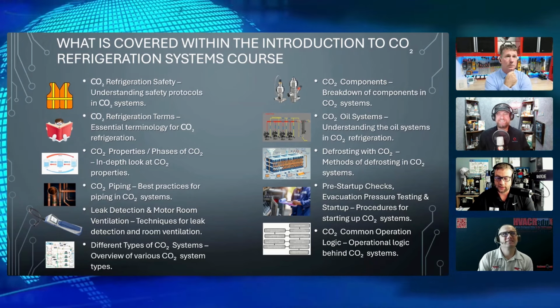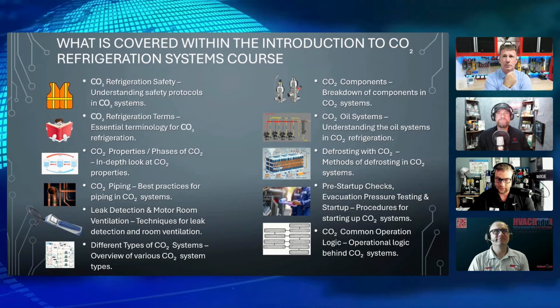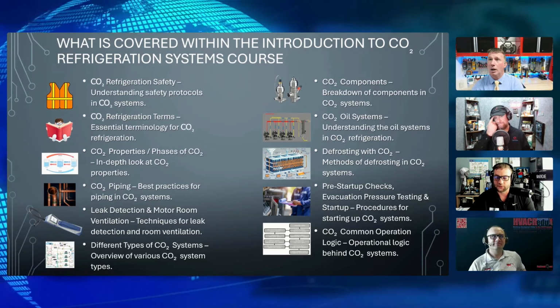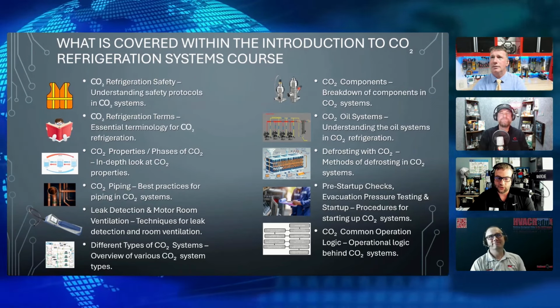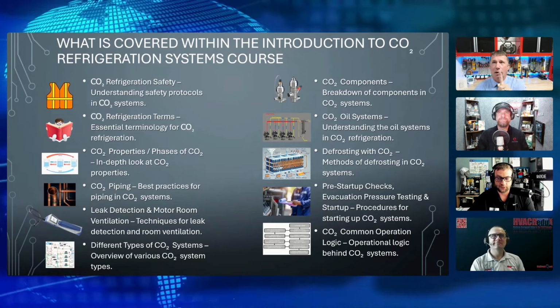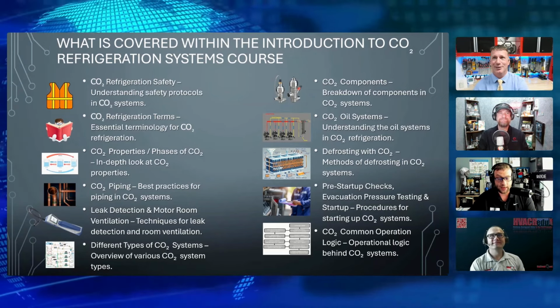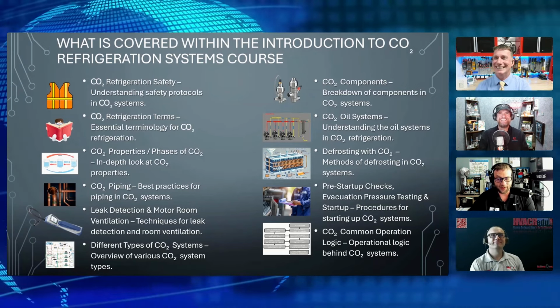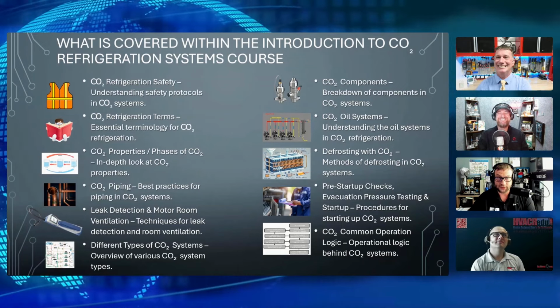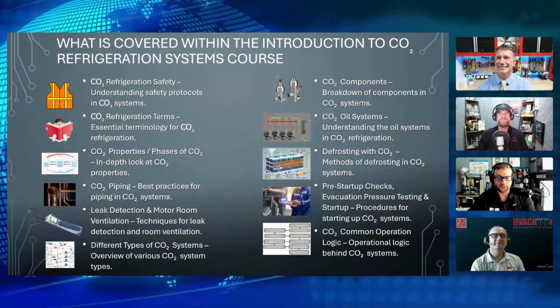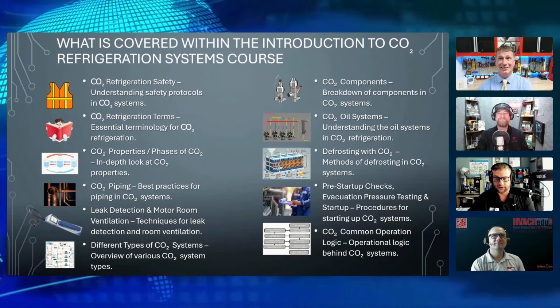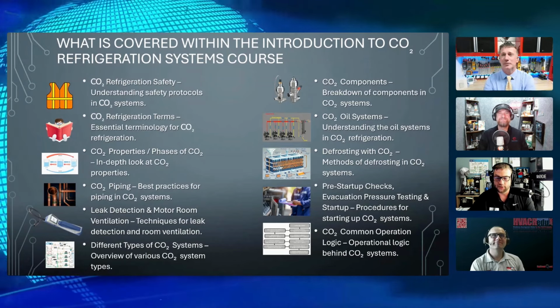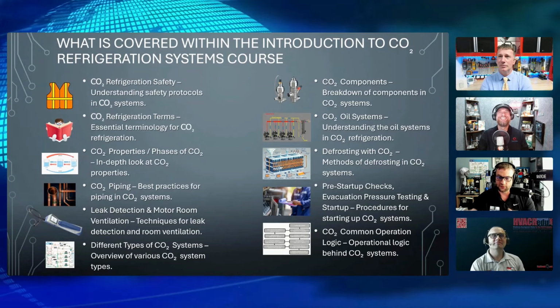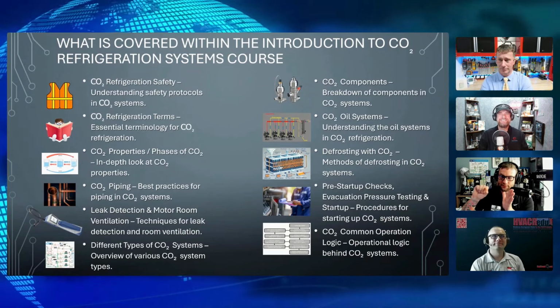CO2 piping: because of the higher pressures, we have to mitigate that somehow. So we can use stainless steel, which is rather expensive, but we also use XHP copper. And you're going to think I'm making this up. Extreme high pressure, that's really what it stands for. Sure. So it's an iron-clad copper, so you can take a magnet to it and it'll stick.